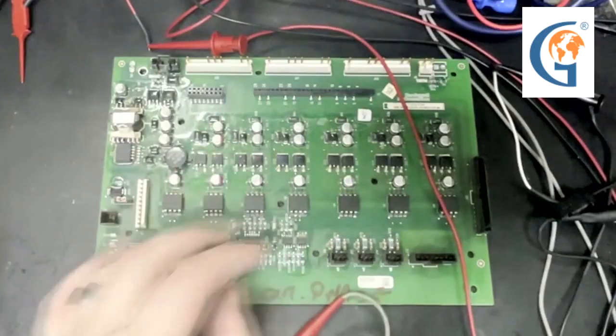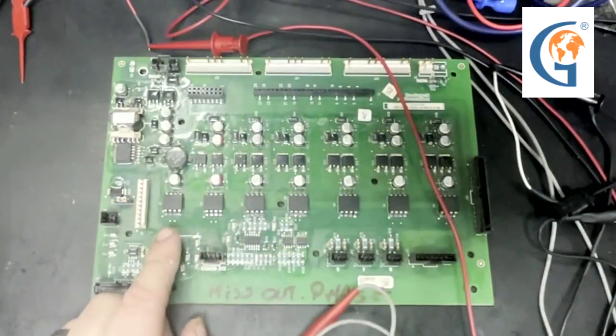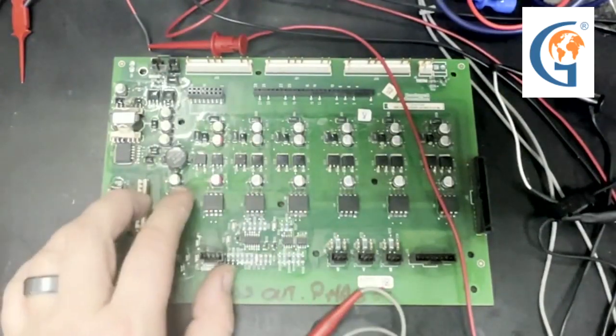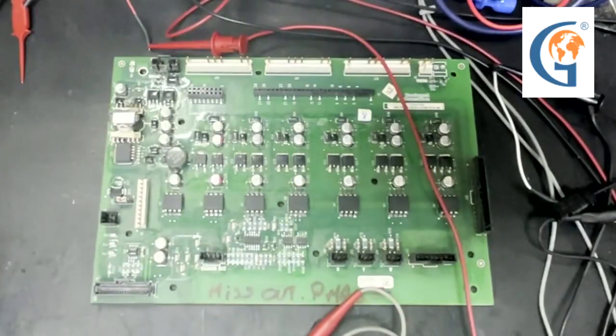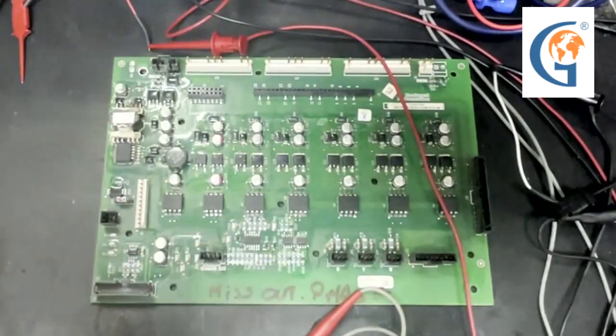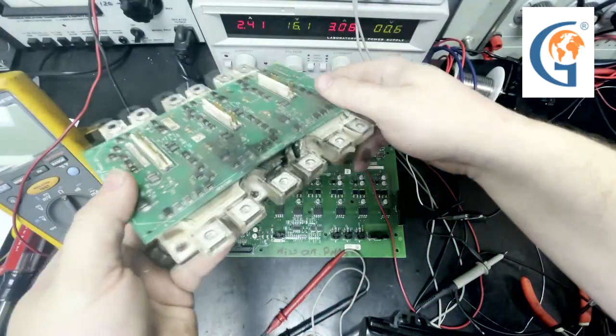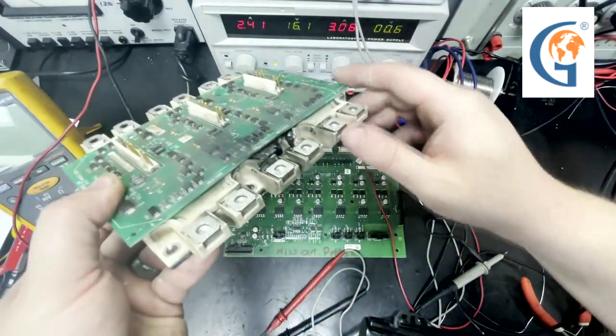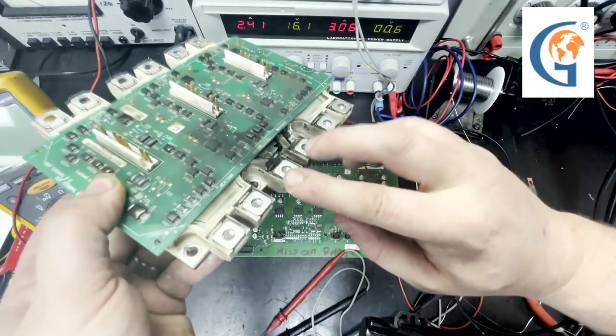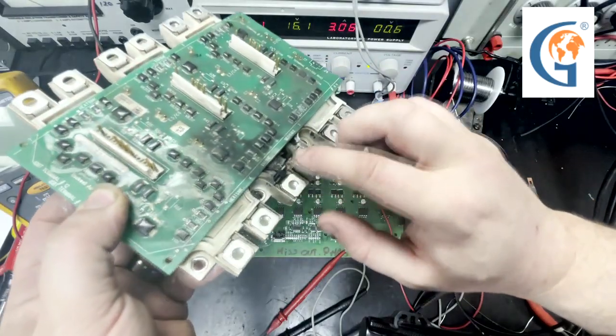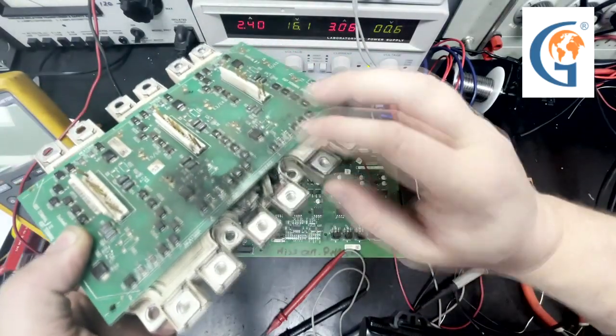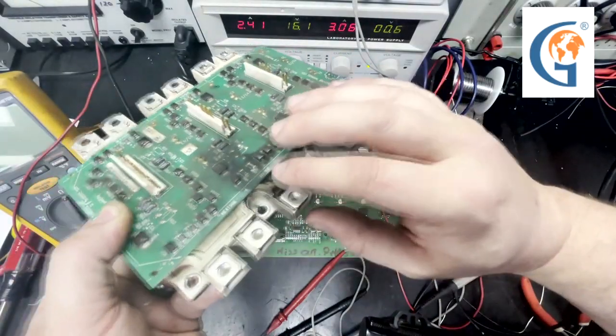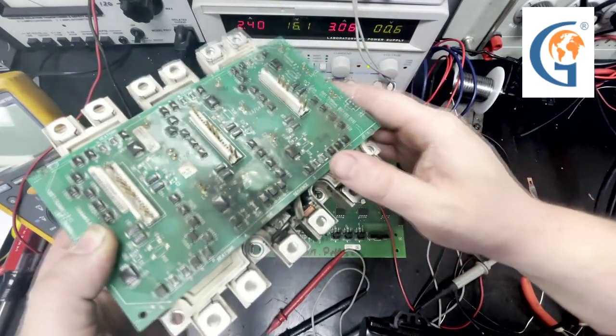This is a firing board from an Allen Bradley PowerFlex 700 drive. It fires the gates to an IGBT in order to control the output to a motor. This IGBT has catastrophic damage from a fire or explosion.